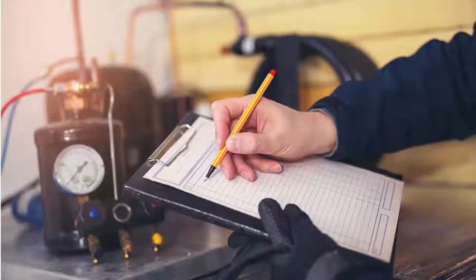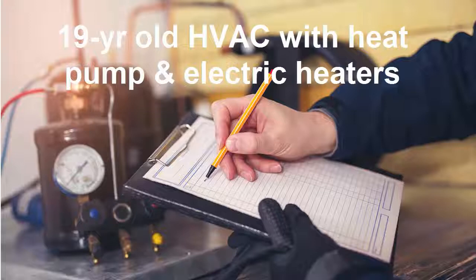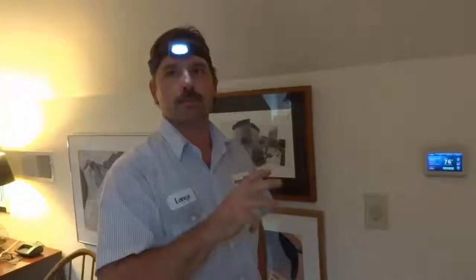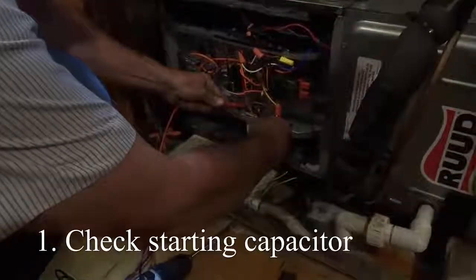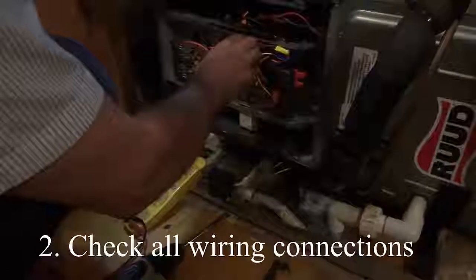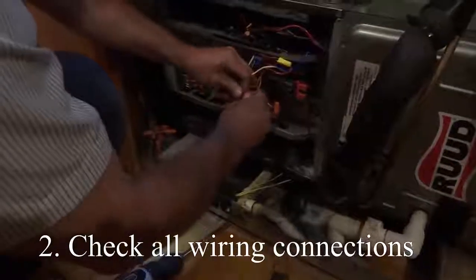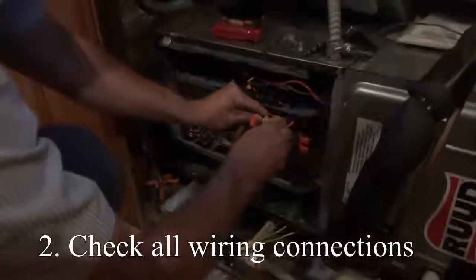In this video, Lance checks on a 19-year-old system installed in a customer's attic. The air handler uses both a heat pump and a bank of 2 electric heaters. Here are some of the points Lance makes as he performs his fall preventive maintenance service. Number 1, the voltage across the capacitor is checked. Number 2, all wiring connections are checked.